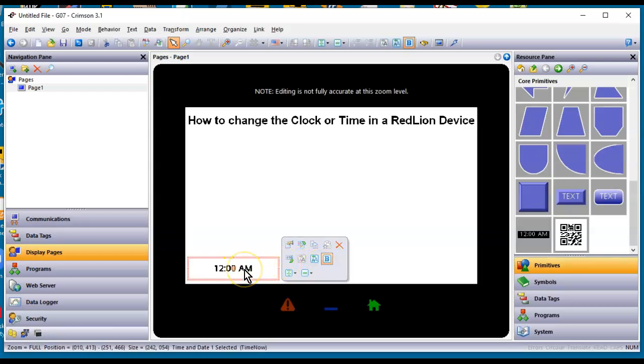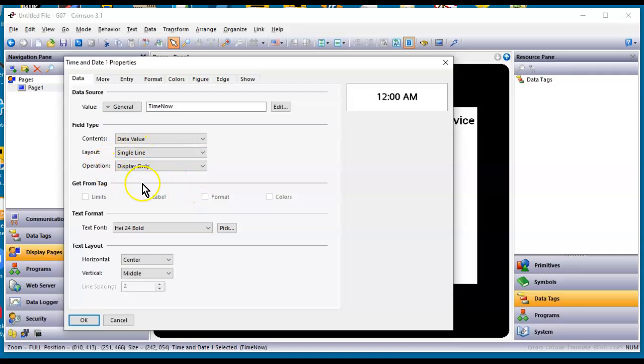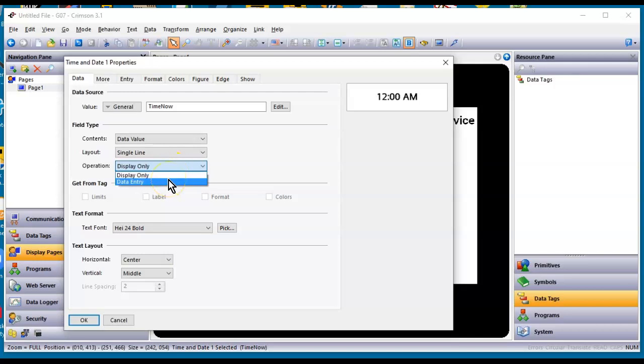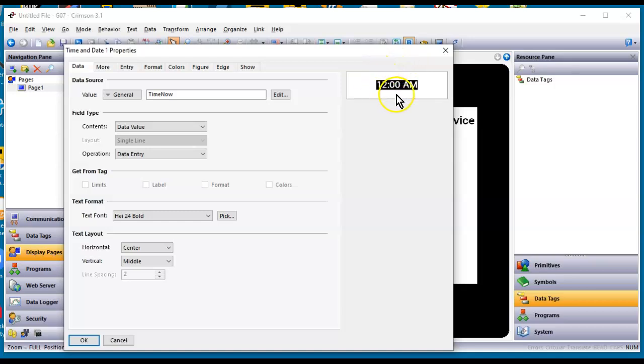However, if you double click on this thing or right click and go to Properties, if you notice right here in the operation display only here, you can make this a data entry field. So if I change this to data entry, notice that the colors get inverted. I've talked a lot about that in class. Anytime you see the colors inverted on any RedLion field, that generally indicates that it's set up for data entry.